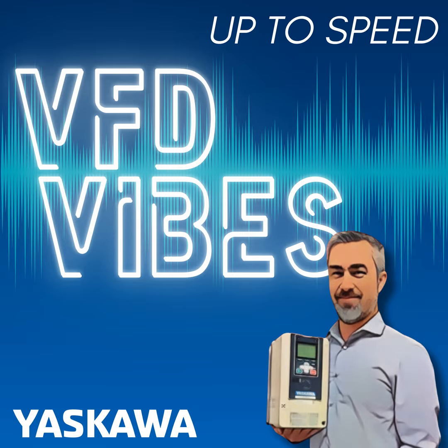Because power is speed multiplied by torque, and power on the input side of the drive is voltage multiplied by current, reducing the power reduces the current on the DC bus and the current coming into the input, and allows the drive to work at some reduced level on these really imbalanced power systems.